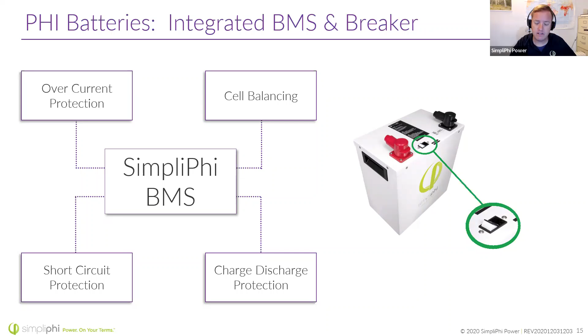When it comes to our batteries, we have a C/2 charge and discharge rating. If anyone's not sure what a C rate is, that's the rate at which you can charge or discharge a battery relative to its maximum capacity continuously. We have a C/2, so if you have a PHI 3.8 battery, the C rate would be 1.9 kilowatts continuously that you could charge or discharge. The PHI 3.8 48 volt is a 75 amp hour battery, so if you want an amp rating, that would be 37.5 amps continuous at 48 volts. This means that you can charge and discharge these batteries relatively quickly compared to a lot of other competitors, and especially compared to lead acid batteries.